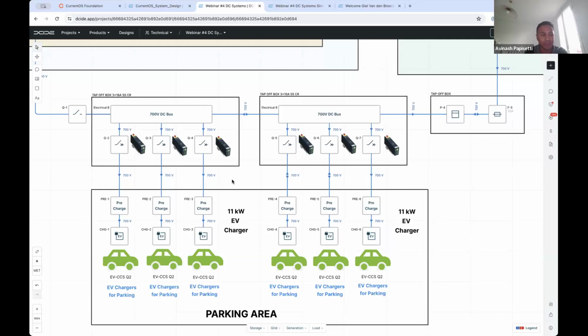Given the deployments we've done in Netherlands, we've optimized a lot on copper distribution. Just because you're converting from a 4-wire system to a 2-wire system, the higher the voltage, the lower the current. Also, on voltage drop, when you distribute sources equally over a network, you can mitigate that problem. Sometimes to mitigate voltage drop, people end up oversizing the copper. So we see good advantages in copper consumption, which directly relates to the carbon footprint of the system versus what we do classically in an AC system.